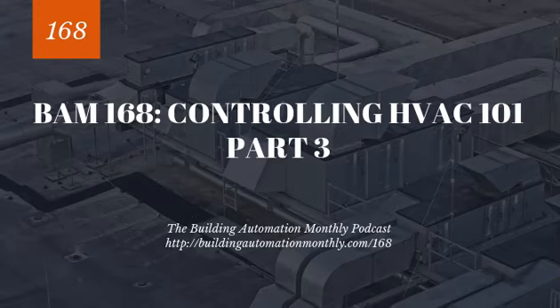It can be calculated manually. I'm not going to take you through that pain, but it is most often calculated by the chiller. Now, this is not to be confused with FLA, which is full load amps, okay? That's really important that you realize, because loading can be a calculation that's just based on a percentage, and it's looking at either temperatures or the refrigerant, or it can be FLA.